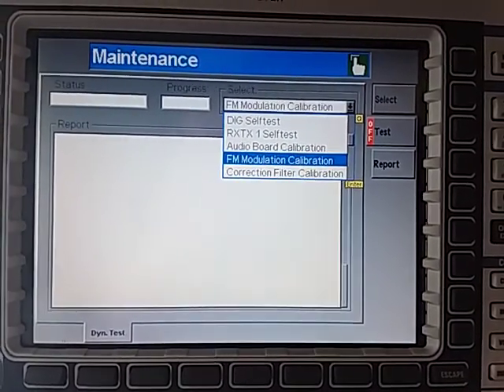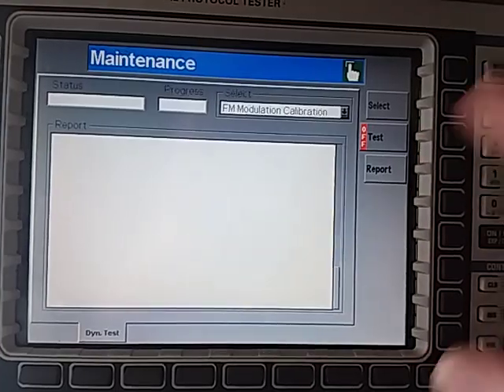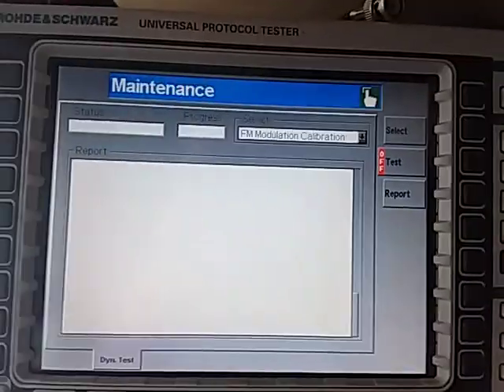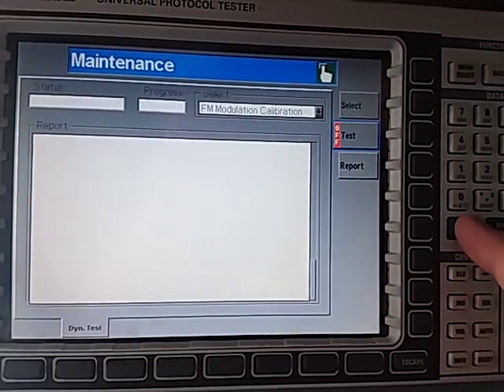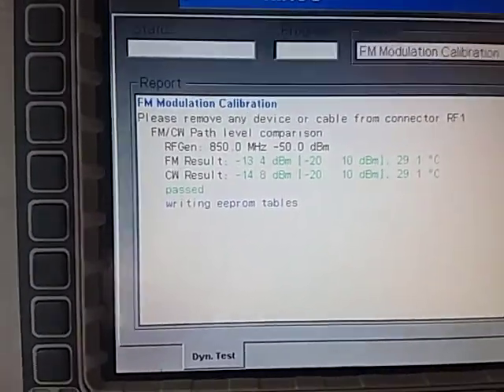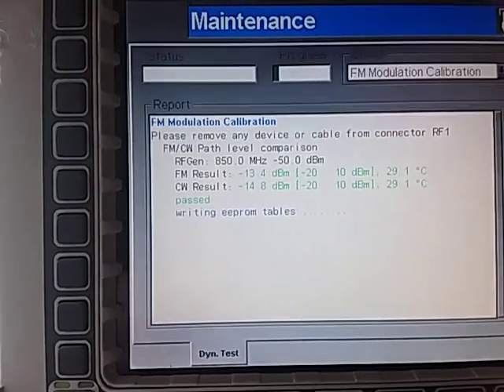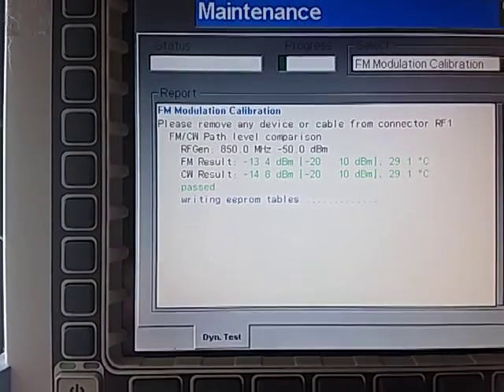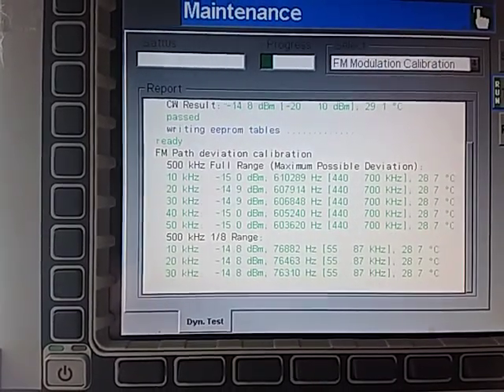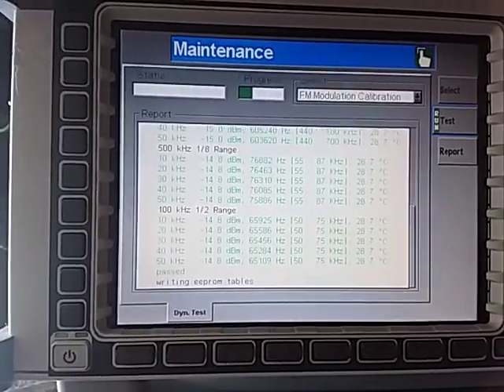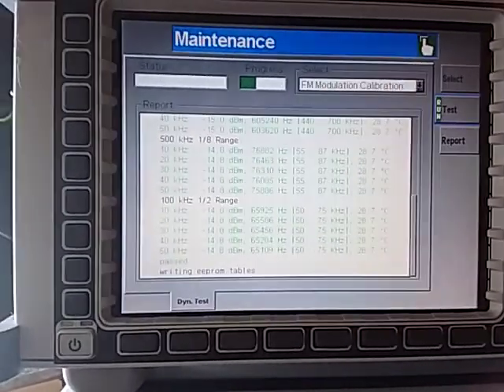This is quite a good one that I always run before if I'm selling it or if I'm doing my analyzer up, if it needs a general maintenance. I'll always run the modulation calibration. It's a simple test. It asks you to put a, this might fail because I've still got my connectors on the front panel. It's telling you to make sure that all the connections should be removed. This will update the calibration tables for it. It's not failing so I will re-run this without the cables on, but holding a camera and trying to get these cables off is going to be a nightmare at the moment, so we won't do that.